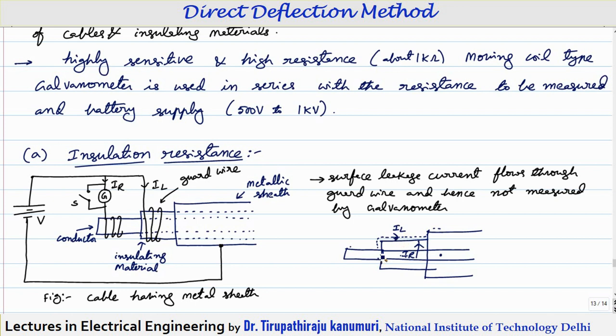Why does this leakage current come? It comes mainly because of the moisture and impurities present in your insulator. Practically, when your cable is exposed to the atmosphere it will absorb moisture, because of which the surface will start conducting and a small leakage current will start passing. Particularly when measuring high value resistances, the current IR itself is very small and is comparable to the leakage current, so proper precaution should be taken.